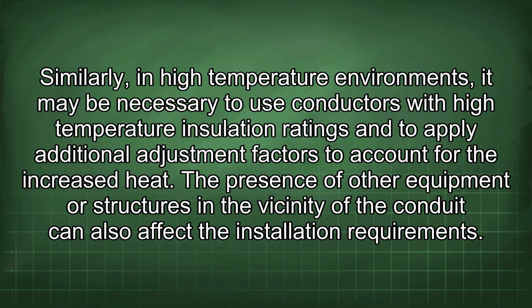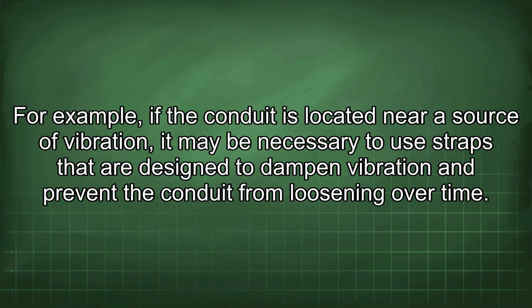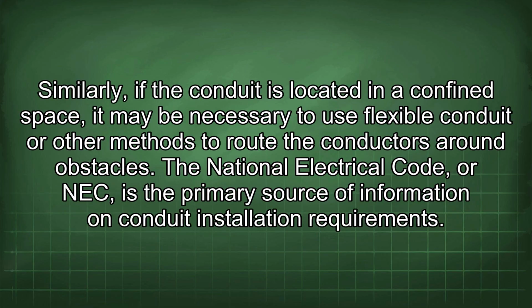The presence of other equipment or structures in the vicinity of the conduit can also affect the installation requirements. For example, if the conduit is located near a source of vibration, it may be necessary to use straps that are designed to dampen vibration and prevent the conduit from loosening over time. Similarly, if the conduit is located in a confined space, it may be necessary to use flexible conduit or other methods to route the conductors around obstacles.